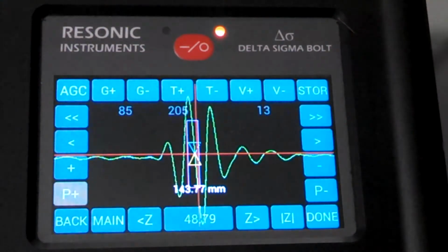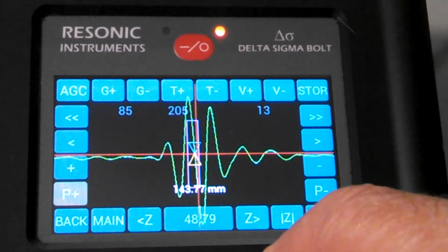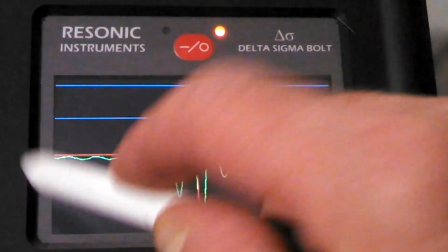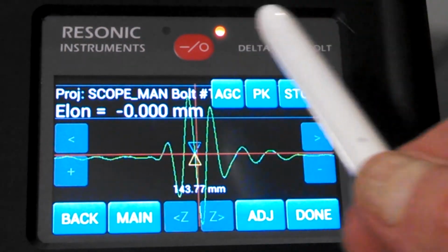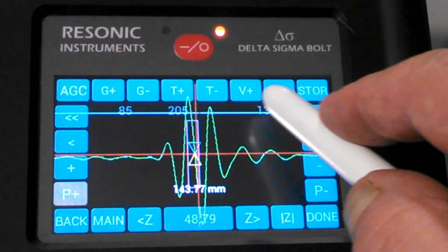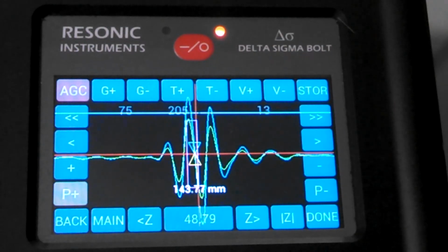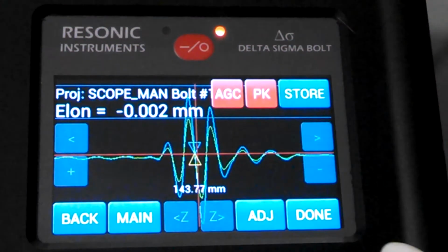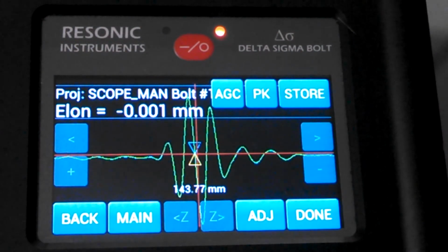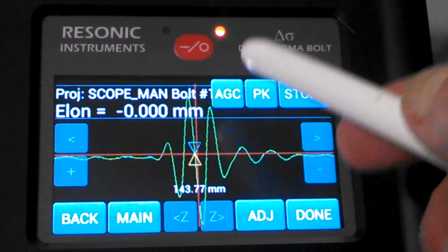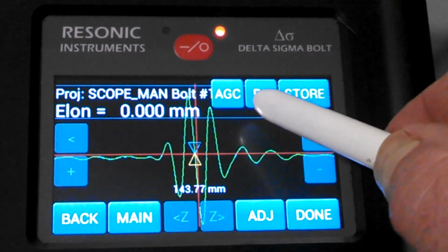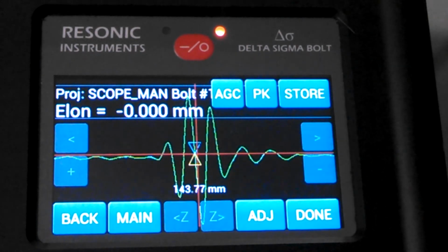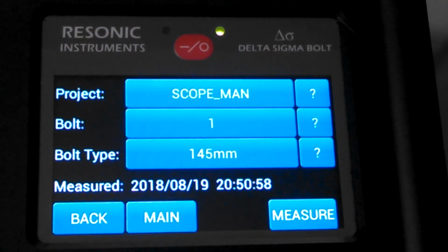You can store the trace from here, so that's stored off into a file where you can go into Excel. You can download it to your PC, go back into Excel, and save and take a look at it. Everything is here, AGC and peak. Do the same thing. Let's go back here and bring the gain down. Okay, so again, back up a little bit, bring the gain down, go back to the main signal, hit AGC, and it comes right back up to the proper trace. AGC works 99.9% of the time. When you come back from taking your zero reading, come back to elongation. If there's a problem with the signal, AGC brings it back up and we're done. So that's the function of the manual oscilloscope in the DS1.